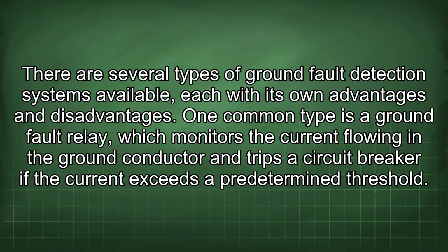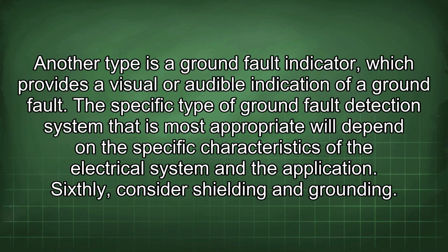One common type is a ground fault relay, which monitors the current flowing in the ground conductor and trips a circuit breaker if the current exceeds a predetermined threshold. Another type is a ground fault indicator, which provides a visual or audible indication of a ground fault. The specific type of ground fault detection system that is most appropriate will depend on the specific characteristics of the electrical system and the application. Sixthly, consider shielding and grounding.